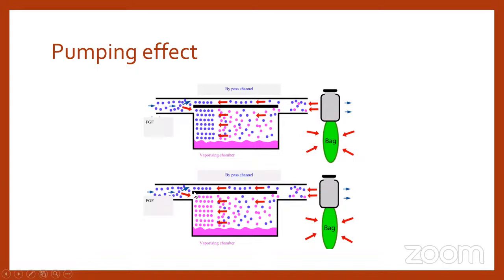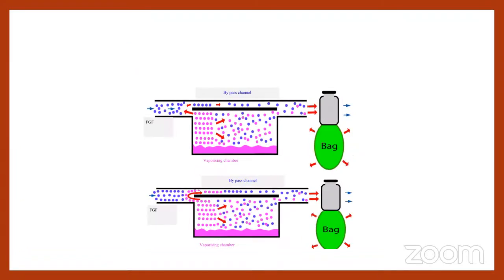Whenever the bag is relaxed, the entire amount of the flow which is already present in the vaporizing chamber and the bypass chamber comes out of the outlet valve, and it will be administered to the patient. So because of this pumping effect, the air present in the bag will re-enter into the circuit, and the concentration of vapor that is present in the circuit will be more when we give the breath to the patient next time. So this is the pictorial depiction of the same. When the bag is inflated, the amount of fresh gas from the bypass channel and the vapor channel will come and enter into the bag, and the re-entry of vapor can be seen in this place at the inlet valve.